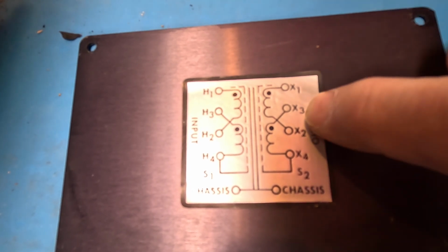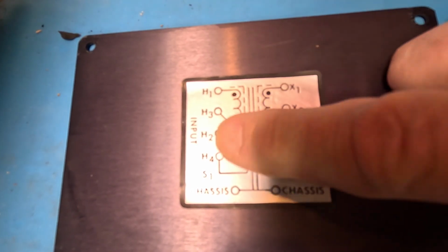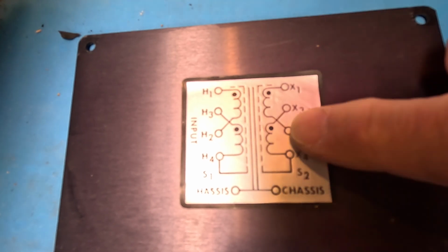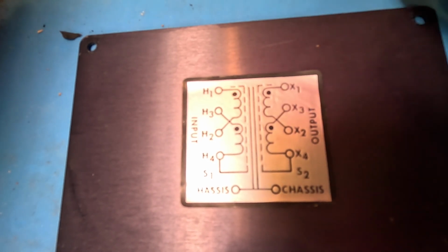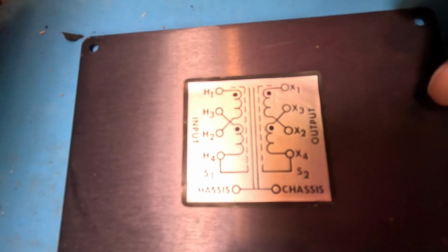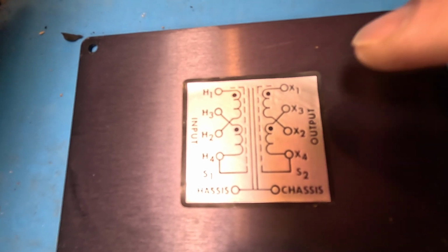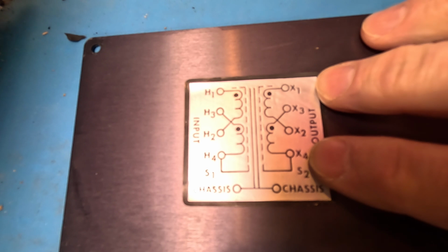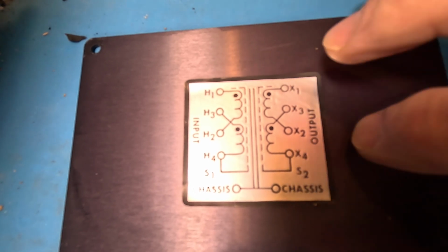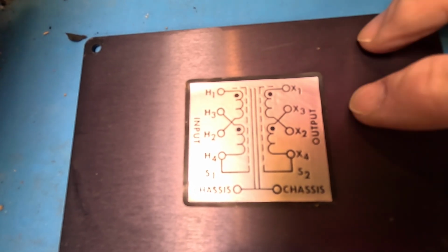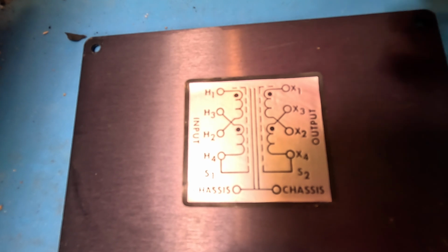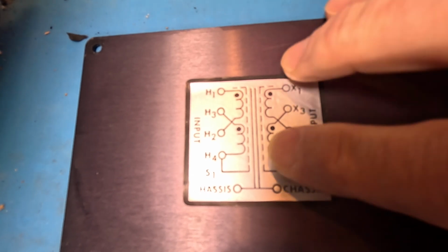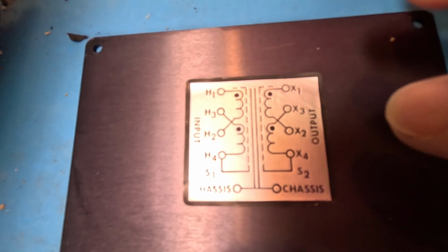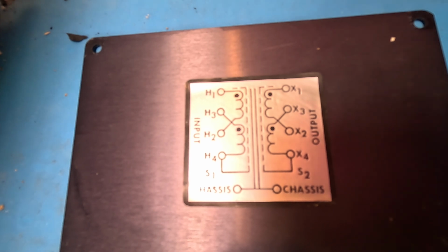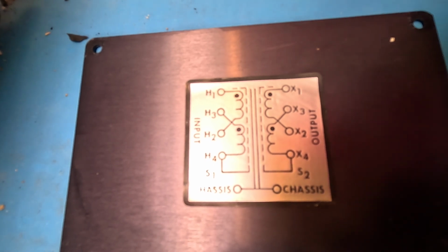But the curious thing is why they didn't parallel the windings, because if they were trying to get a lot of current to this that it's rated for, 2500, then they would have needed to put these windings in parallel. Or if it's 240 in series, you'd have to use all the windings to get the full power rating. So if you're only trying to get half, then you're okay. So yeah, I'm not worried about this. It looked like a really super nice transformer. Now I'm kind of worried.